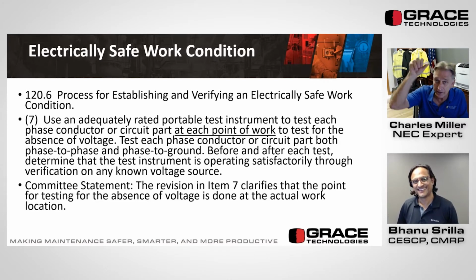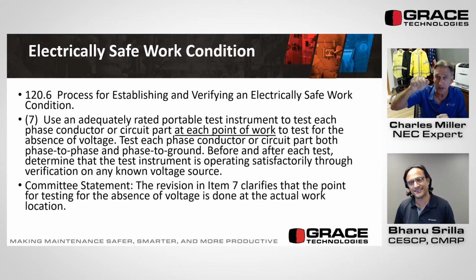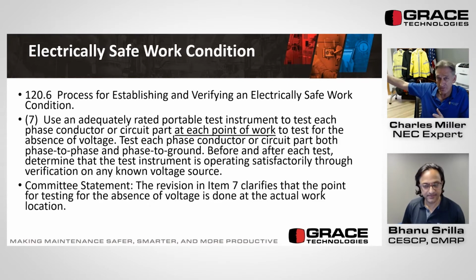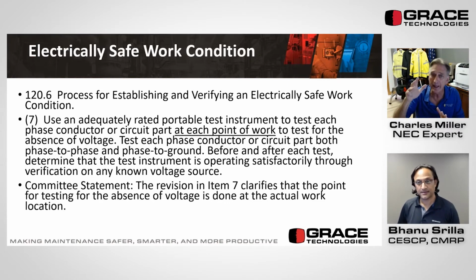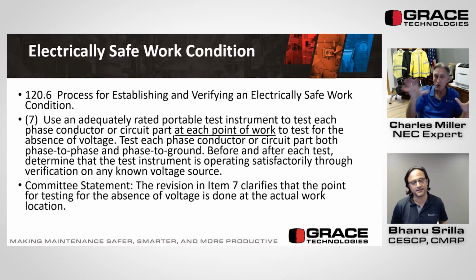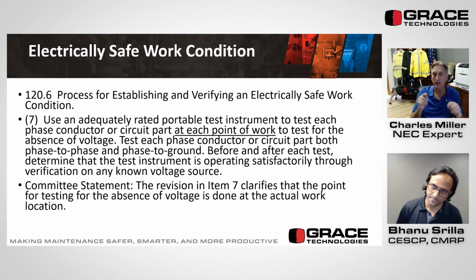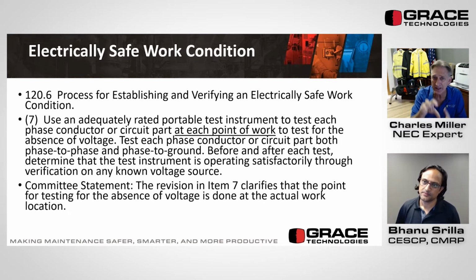Then we test our meter again on any known voltage source at the breaker where it comes in the top, at the disconnect switch where power is coming in, because we de-energized it upstream. Well, in order to work in that whole cabinet, don't we have to do the same thing at every device, at every terminal, at every conductor in that industrial control cabinet?